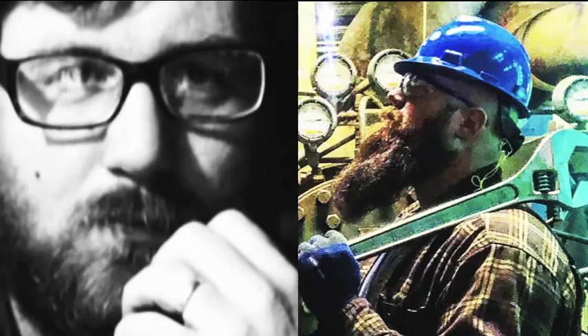Wow. That's a lot of stuff, especially on your first trip there. Is that right? It was my first trip there. We had one guy there a few weeks before that did an initial kind of a light PM on some of the other equipment. So he had been there on site and he had looked at the air handler and changed some belts and filters, etc. But he didn't look at the water side. Now, do they consider that no harm, no foul? You weren't supposed to know that sort of thing, or were they actually agitated with your company? No, not at all. You mean as far as knowing to turn the boilers back on? Yes. No, she had never told me they were shut off.